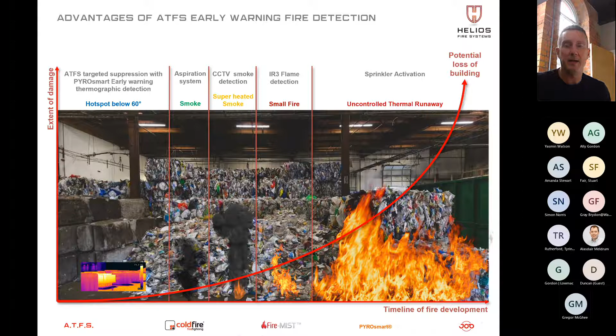Ewan actually quite rightly said there's a part of this slide missing, which we didn't add in, which is customers that haven't got any protection at all. And that goes straight to potential loss of building because they don't detect it, they can't suppress it. With ATFS, we can be right back here. We don't have the fire, we have the hotspot. Or even if it's a compromised lithium-ion battery, which has been hit by the blade of the loading shovel that creates an immediate fire, then we can deal with it. The camera system will see it and it will actually detect and put the fire out. So let's give you a better insight to technologies that are on the market, where they fit in the timeline of the fire development, on how big the fire can actually be before it actually takes action.